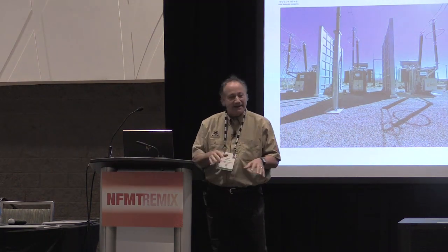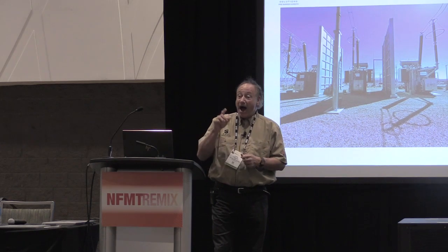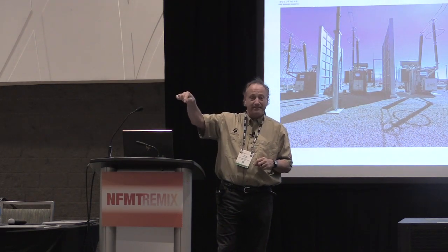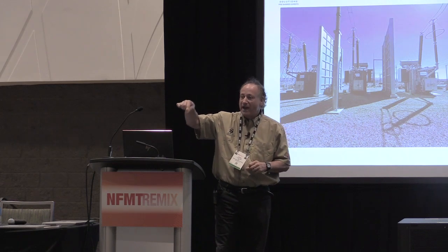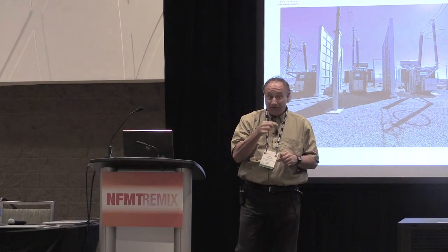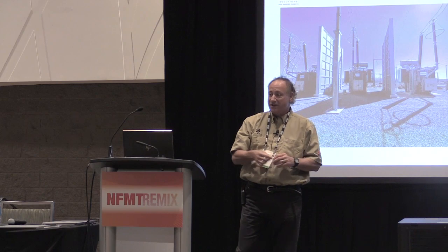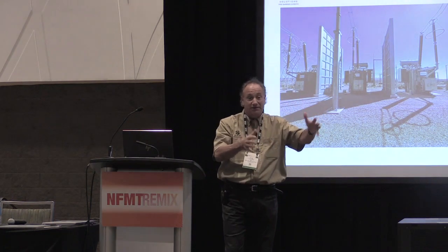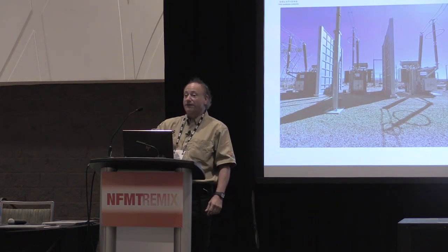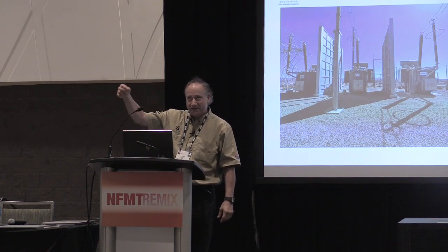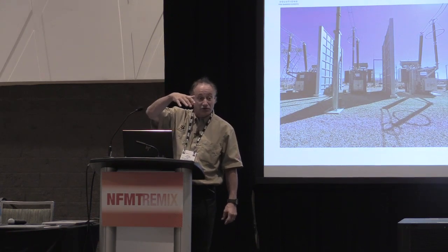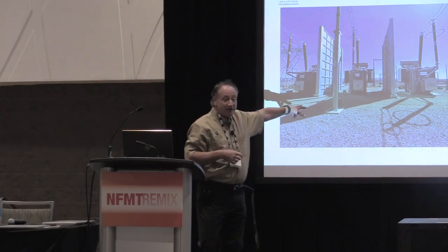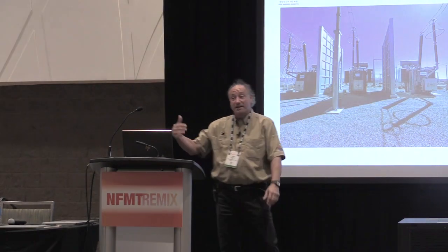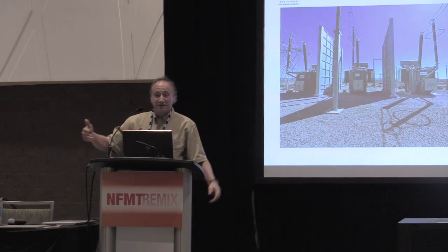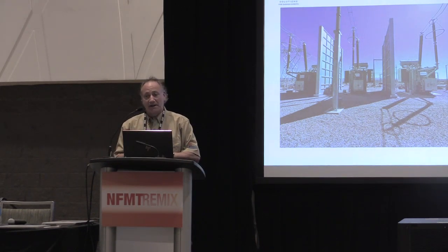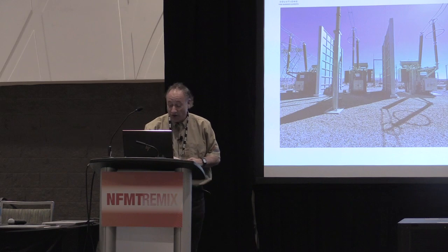9 out of 10 old timers will tell you they don't want to be there the day a new system starts up, because new ones fail just as much. The old one's been running for 50 years. Yes, it requires protection and compliance and has other issues, but even in new installations, the transformer suppliers you work with are going to require this as part of the job now. There's no grandfathering. If you're doing new construction, you really need to think about this.